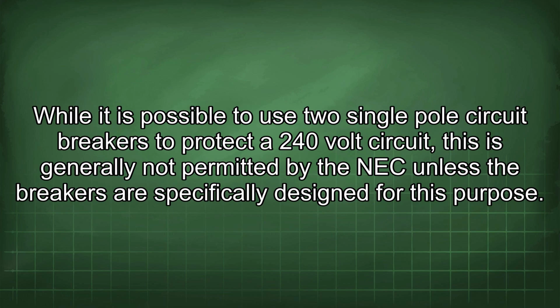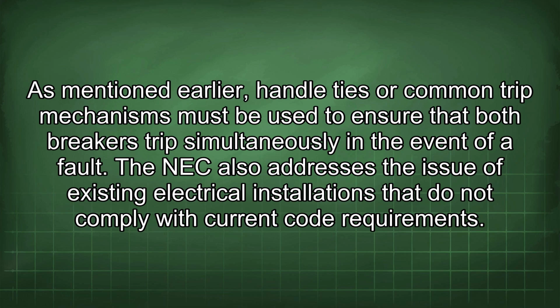While it is possible to use two single-pole circuit breakers to protect a 240-volt circuit, this is generally not permitted by the NEC unless the breakers are specifically designed for this purpose. As mentioned earlier, handle ties or common trip mechanisms must be used to ensure that both breakers trip simultaneously in the event of a fault.